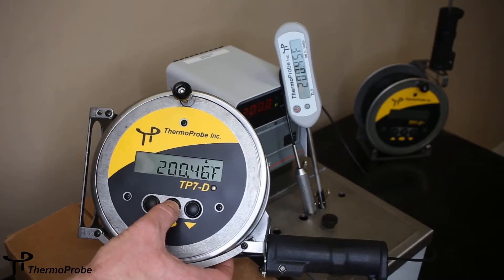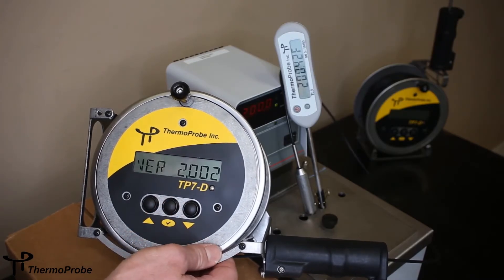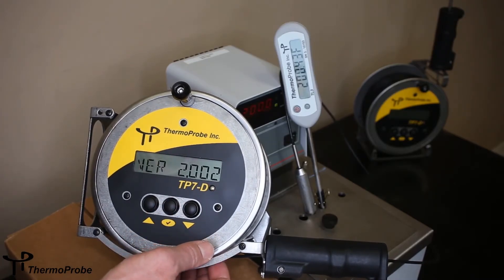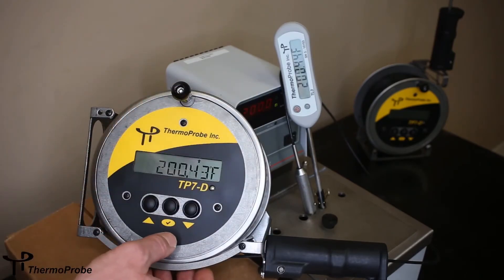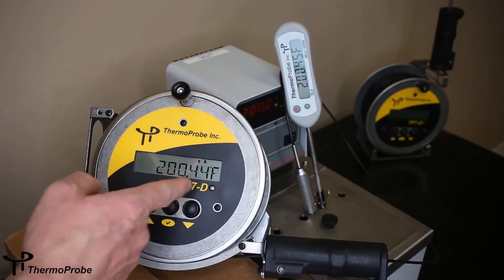To save that, we need to power the instrument off, and it's always a good idea to go back and verify that your adjustment still matches your reference at each point it was adjusted. So, 200.43, 200.45, 200.44. Yep, that's good.